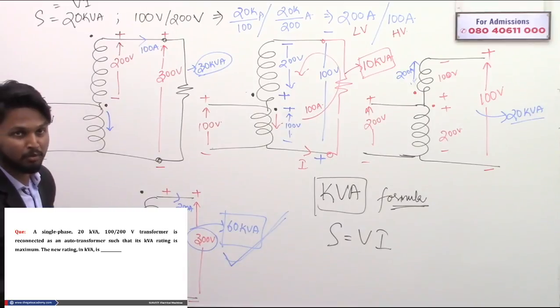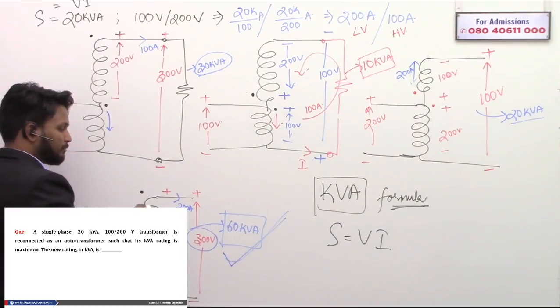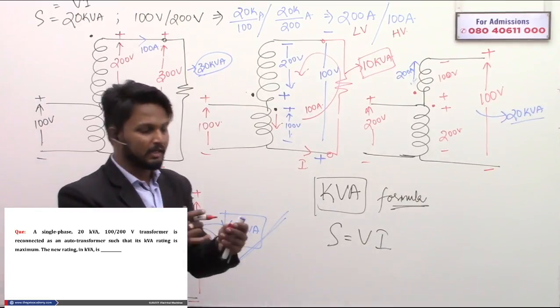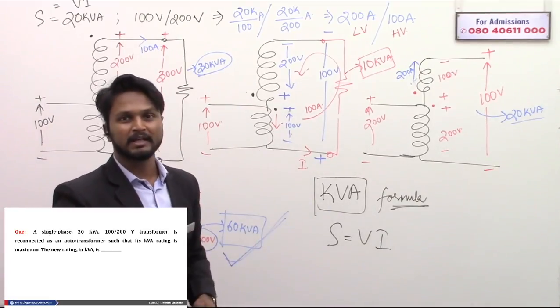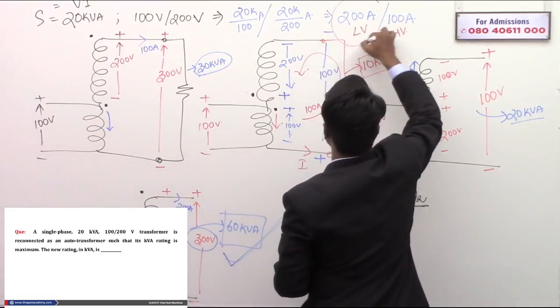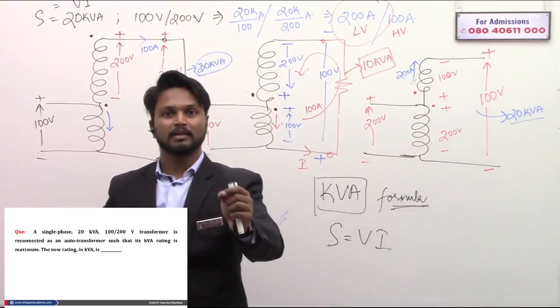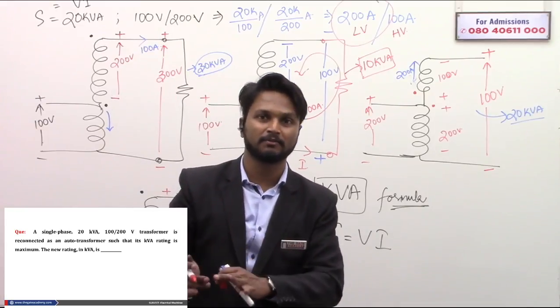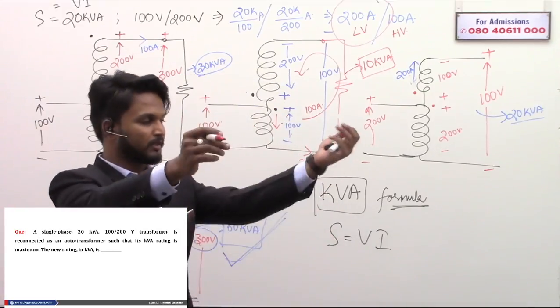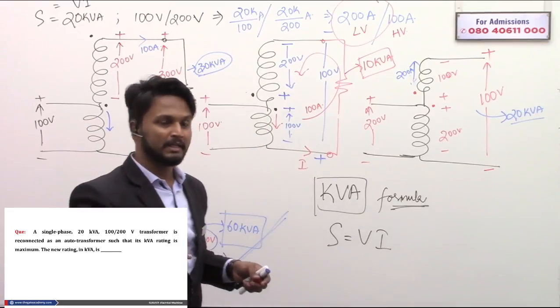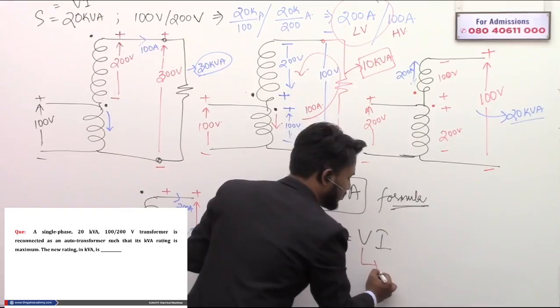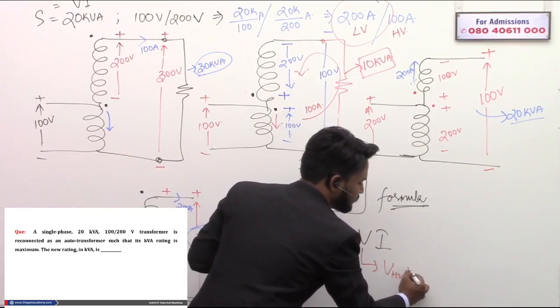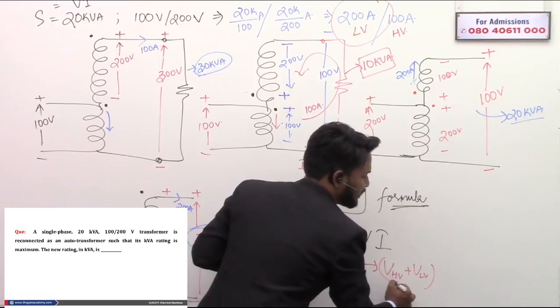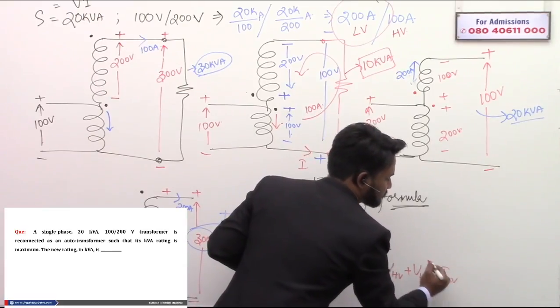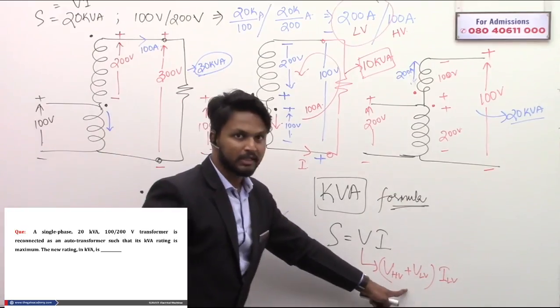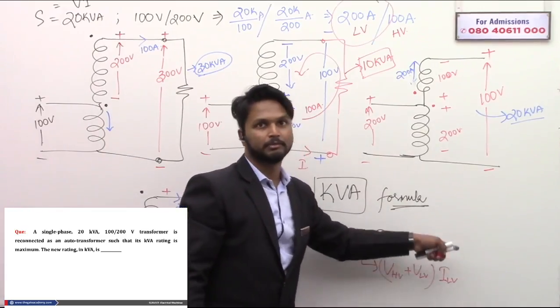You should obtain maximum voltage and maximum current out of the HV and LV windings - whichever can carry maximum current. LV can carry maximum current. So the maximum rating of an auto transformer constructed from a two winding transformer is nothing but the sum of LV and HV voltages, VHV plus VLV, multiplied by ILV.